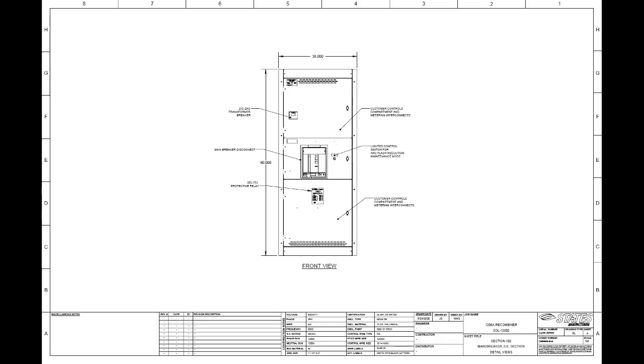And then simply a main disconnect breaker that, once again, they might have a protective relay, a zigzag transformer breaker connection, and then still there is room in the different compartments for customer metering to be inside of it. A lot of the times, though, we'll see in the field they actually end up mounting them either on a pedestal or unistrut to the side of the equipment when they do a little bit smaller footprint installation like this.